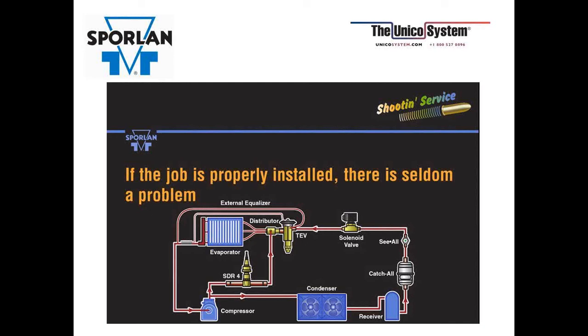What did you recommend, Ron? At least 500 microns. And then a triple evacuation is always better. Break it with nitrogen and do it again. But if the job is properly installed, there's seldom a problem because it is a closed system. They shouldn't have any issues.